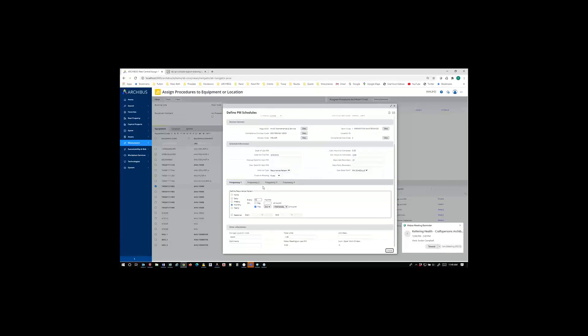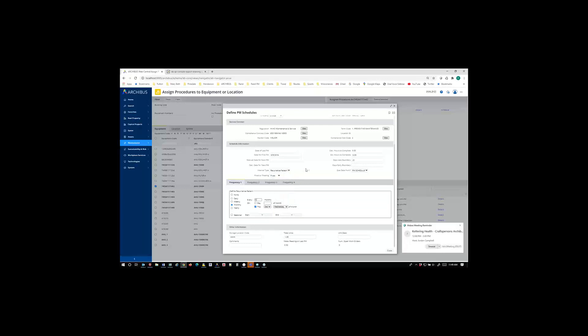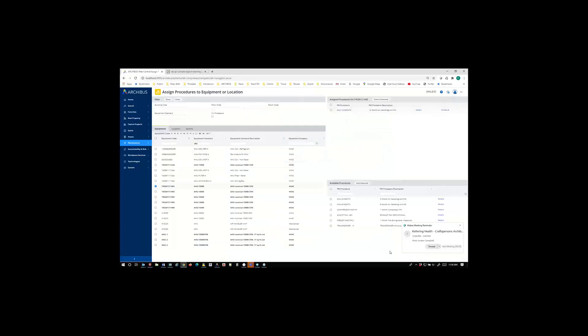There is a list of procedures that you can select from and then assign to that. And once you have a procedure assigned to a particular piece of equipment, you can set up the schedule. So you have the schedule, you determine what kind of frequency you want to do it, what kind of interval type, you can do it specifically in days, weeks, or year, or you can have a recurrence pattern, more or less like Outlook's setup. And then you can also do fixed or floating. Fixed meaning it's going to generate a work request on every episode of the frequency. Floating meaning it will only start the next clock after you've completed the one you have now.